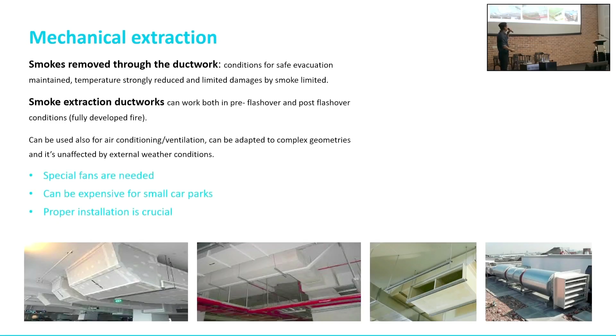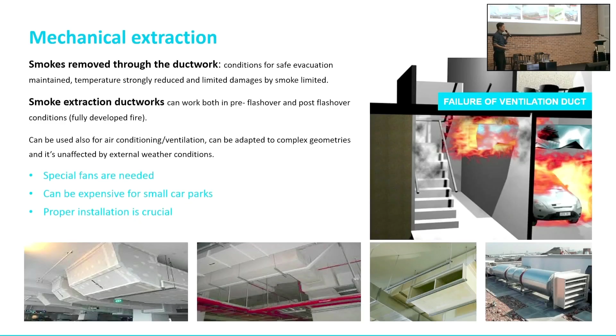So if you have a huge area, the passage has to go through multiple compartmentation before it can get out of the building. So before this smoke is able to get out of the building, if the duct is not fire-rated, it will just collapse and defeat the entire purpose of your smoke extraction system.